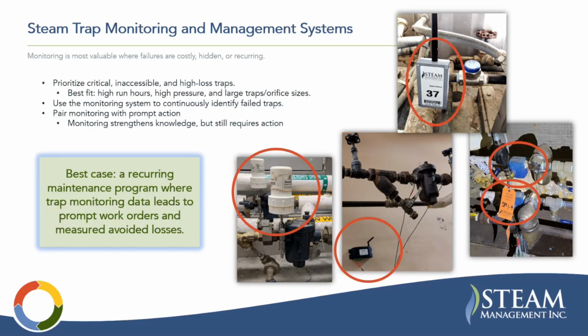So here's some examples of different trap monitors. Basically, when you monitor steam traps, you're going to want to prioritize critical, inaccessible, and high loss traps. So the best fit is traps with high run hours, high pressure, and large orifice sizes. You're going to want to use the monitoring system to continuously identify failed traps, but you're going to want to pair that with prompt action.